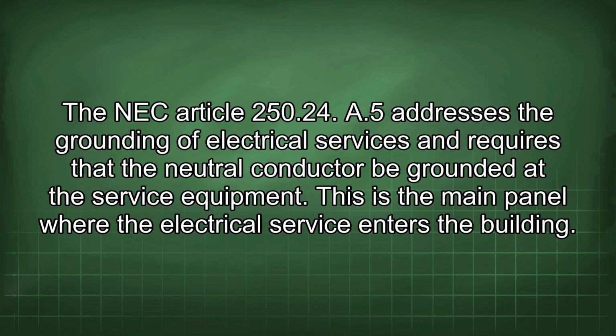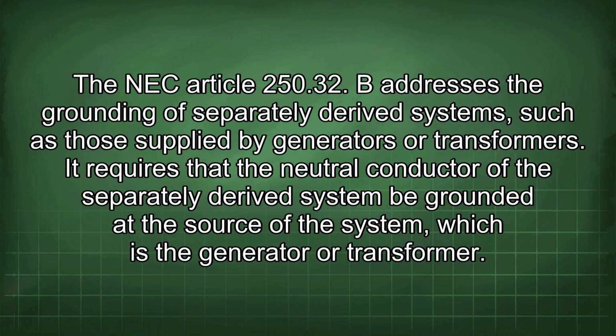NEC Article 250.24(A)(5) addresses the grounding of electrical services and requires that the neutral conductor be grounded at the service equipment. This is the main panel where the electrical service enters the building. NEC Article 250.32(B) addresses the grounding of separately derived systems such as those supplied by generators or transformers. It requires that the neutral conductor of the separately derived system be grounded at the source of the system, which is the generator or transformer.